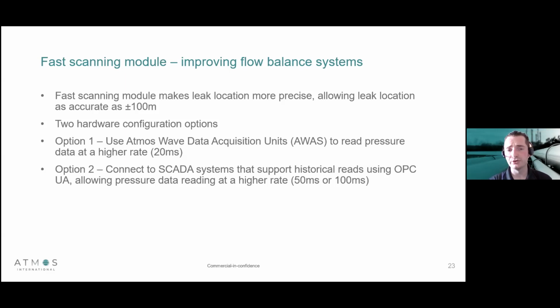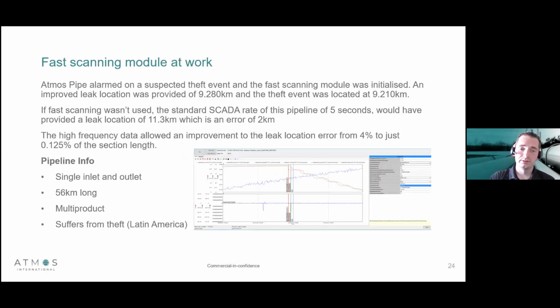So what Atmos has done with our software packages is adopt hardware solutions into that. We can utilize our own data acquisition units, or we can get SCADA systems now to sample at higher rates. What that allows us to do is to collect data at a higher frequency, and has allowed us to improve our location from plus or minus a kilometer to plus or minus 100 meters, which means we've removed that inherent weakness. Here's an example. This was on a pipeline in Central America.